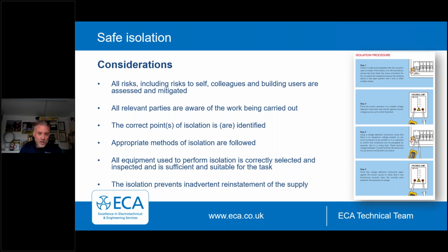Many times a pre-check or testing of where the isolation points are never identified. So if you're working, for example, on a ring final circuit or other outlets, it's important that you identify every single outlet that you wish to make dead, and also the sources. Appropriate methods of isolation are followed. Equipment used to perform isolation is suitably selected and inspected and sufficient and suitable for the task. So just as an example, we've got a Martindale tester here. So it's ensuring that the probes are good, the cable leads are good, and it proves right when you put it on a proving unit.